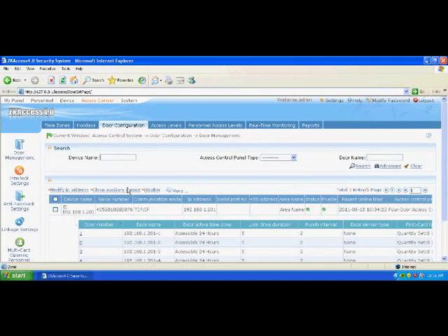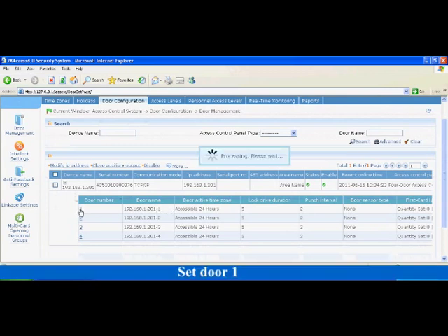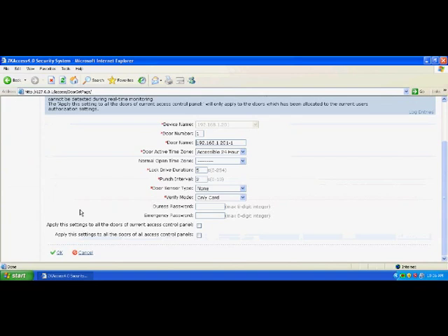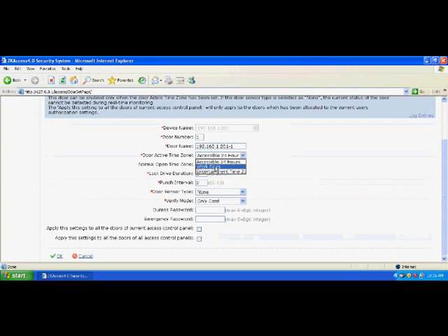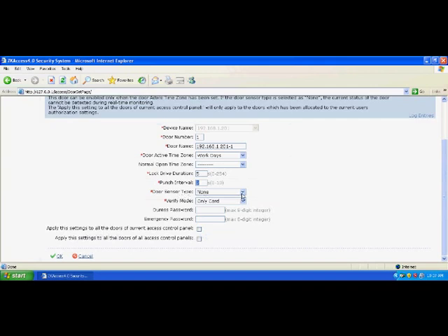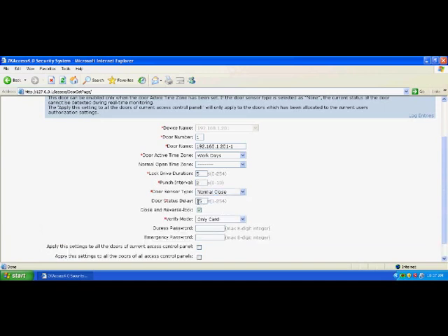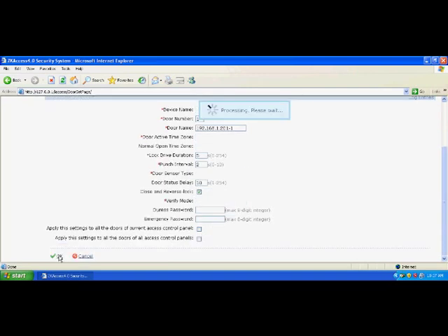Step 5: Door settings. Set door 1 and select workdays for the valid time zone. The lock drive duration is 5 seconds, the door sensor type is normal close, the door status delay is 10 seconds, close and reverse lock is selected, and verify mode is only card. In the workdays time zone, you can open the door by verifying your card, and the door is opened 5 seconds after your card is verified. When the door sensor type is normal close, the door is always closed upon power on and always opened upon power off. The door sensor checks 10 seconds after the door is opened, and the lock is automatically closed after the door is closed. Click OK to complete the settings.